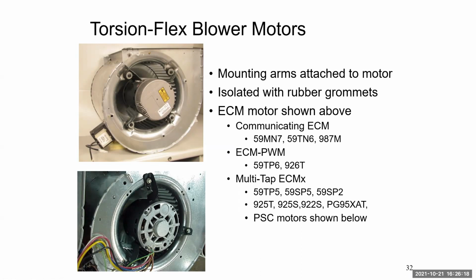If you're getting the 41 motor communication fault, it can be your motor, your module, or your board. But with the ECMs, you can take your module off, pull that, pop it, get your Molex taken apart and look at it. Inside, you're going to find that resistor. It's about the size of a half-dollar, black, about an eighth of an inch thick. Check that for discoloration, cracks, anything like that. Normally, if they crack, they start creating a white film around that crack. Or if the whole thing just looks charred white-black, it's blown. Replace that module.